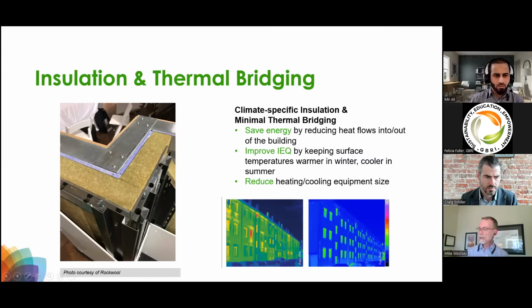The result is shown in a before and after thermogram, with before on the left and after on the right. The temperature scale shows red and yellow as warmest, and blue and dark blue as coolest. This building was clearly heating up its skin much more than the retrofit project. You can see the windows performing better too, with less yellow and almost all green, so it's pretty homogeneous. That plays a role, of course.